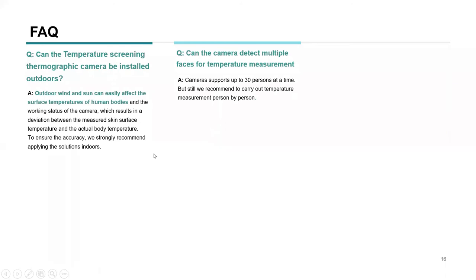Frequently asked questions: Can the thermographic camera be installed outdoors? No — outdoor wind and sun can easily affect skin surface temperatures and the camera's working status, causing deviation from actual body temperature. We strongly recommend installing indoors, away from wind and sun. Can the camera detect multiple faces simultaneously? Yes, up to 30 persons at once, but we still recommend person-by-person screening using a screening channel.